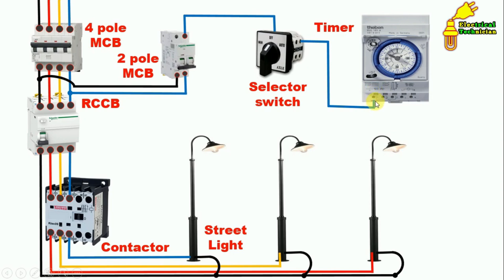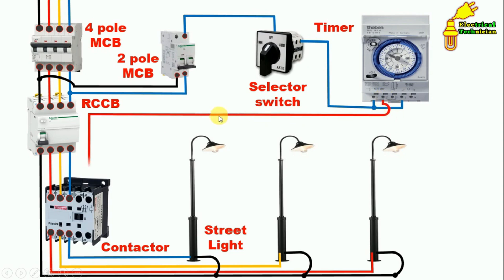I connected the wire with the NO contact — terminal number one — of the timer. To operate this timer, it needs power supply. Here L and N terminals are marked; connect phase supply to L and neutral supply to N. The wire connected through the selector switch is looped and connected to the L terminal of the timer. At the common terminal of the timer, connect one wire and connect it to the A1 terminal of the contactor.